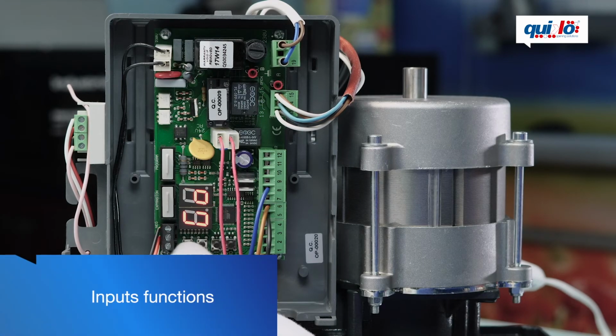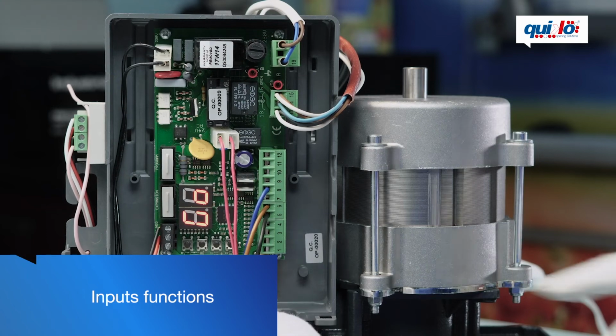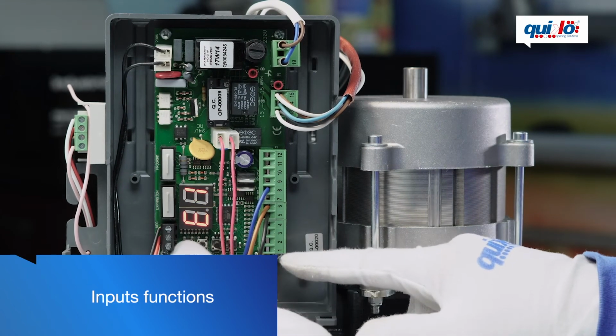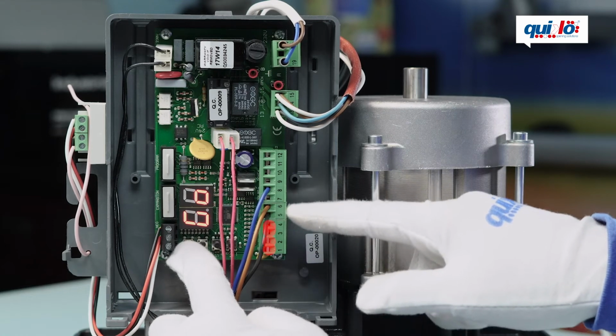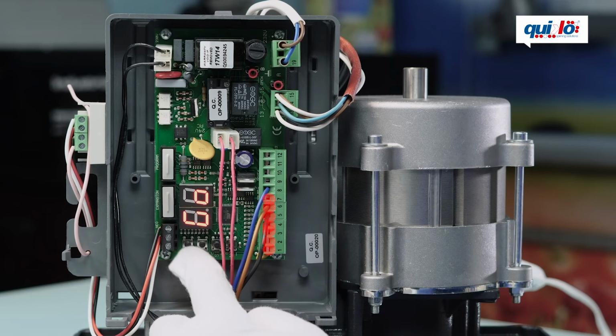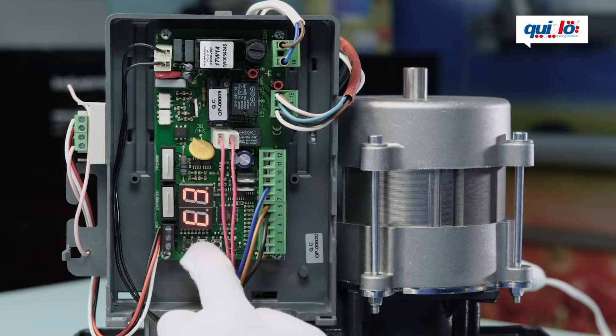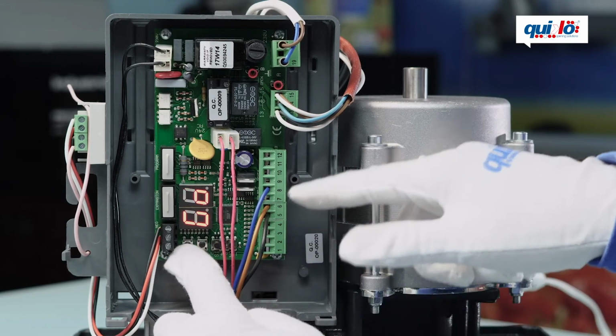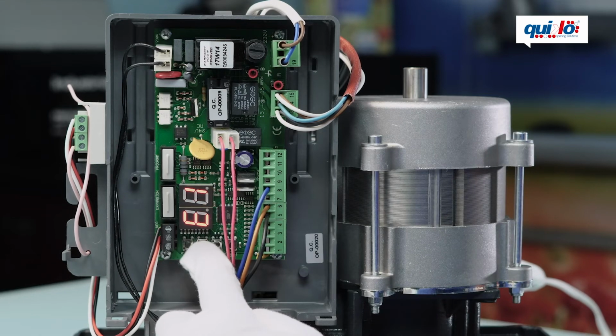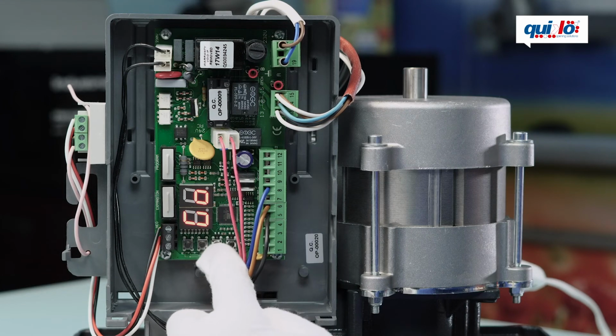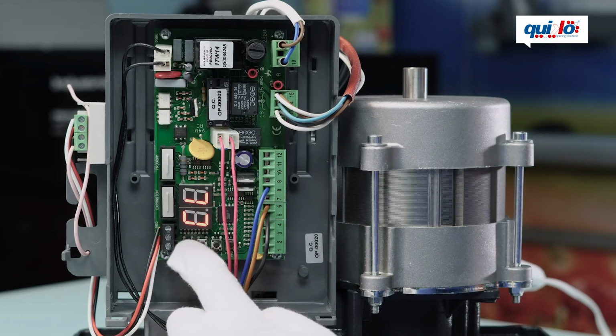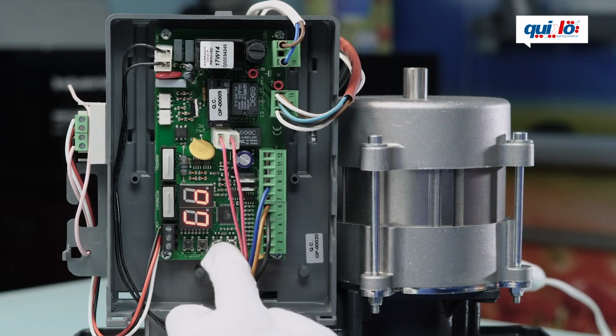Then you have all the E parameters that are related to terminal block connectors number 1, 2, 3, 4, 5, 6 and 7. By means of E1, 2, 3, 4, 5, 6 and 7, you can set how you want each terminal block connector to work. For example, the E1 parameter, per standard, is set to give a start signal, but you can also set it to open only or close only.